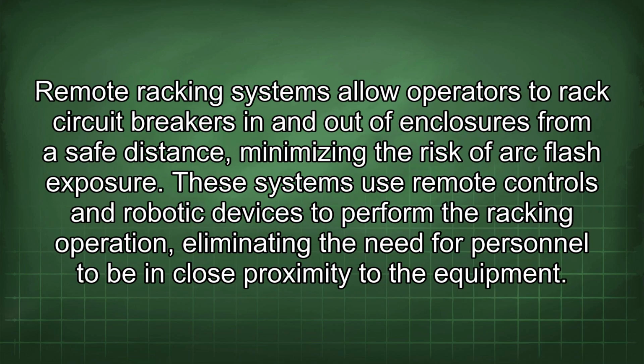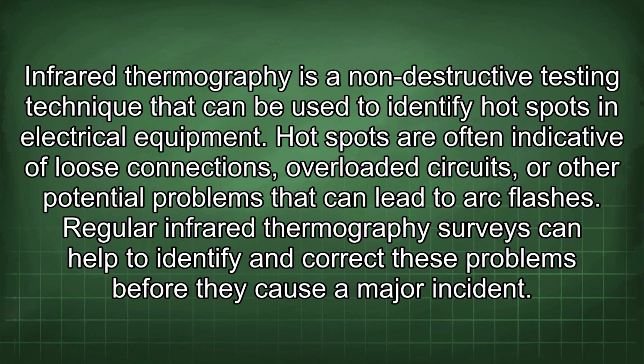Remote racking systems allow operators to rack circuit breakers in and out of enclosures from a safe distance, minimizing the risk of arc flash exposure. These systems use remote controls and robotic devices to perform the racking operation, eliminating the need for personnel to be in close proximity to the equipment. Infrared thermography is a non-destructive testing technique that can be used to identify hotspots in electrical equipment. Hotspots are often indicative of loose connections, overloaded circuits, or other potential problems that can lead to arc flashes. Regular infrared thermography surveys can help to identify and correct these problems before they cause a major incident.